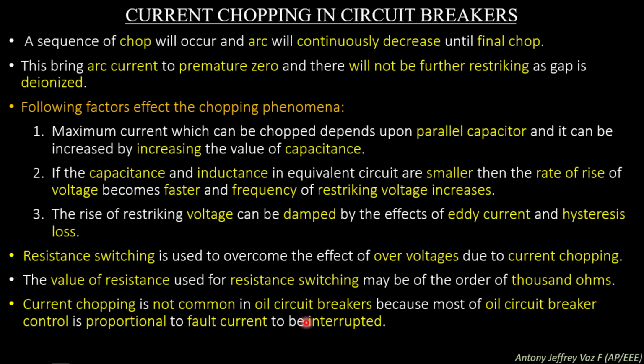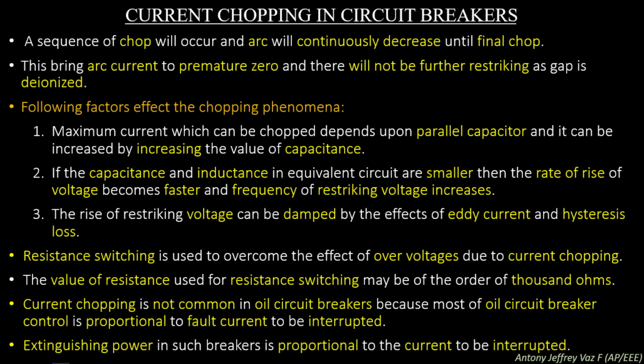The phenomenon of current chopping is not present in oil circuit breakers because the dielectric medium of the oil does not allow current chopping. So the extinguishing power in such breakers is proportional to the current to be interrupted. So the power of the circuit breaker depends on the current to be interrupted.